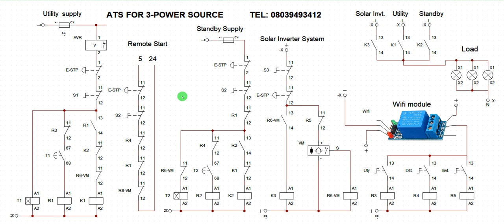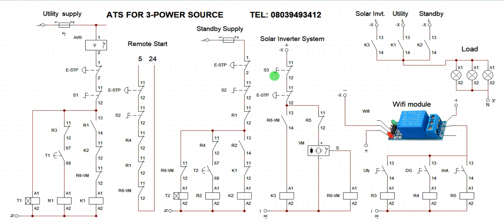Conventionally, ATS is designed according to end-user requirements. This particular logic is designed based on end-user request. The primary source of power is the solar inverter system, seconded by the utility, and lastly the standby genset. When solar is not available, utility becomes active, and in the absence of utility, the genset gets energized.